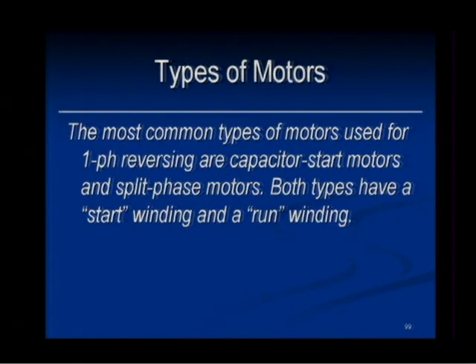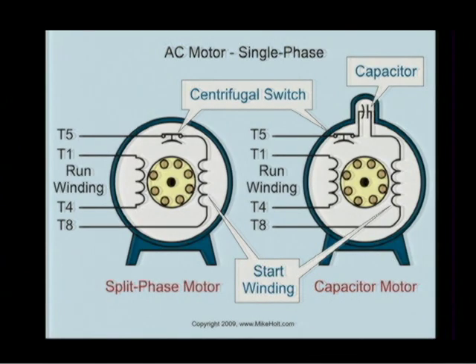The most common types of motors used for single-phase reversing are capacitor-start motors and split-phase motors. Both types have a start winding and a run winding. Are they actually numbered T1, T5, T4, and T8? Very commonly, there are some variations, but that's kind of a standard. But if they weren't this number, would it be marked somewhere? Is that on the nameplate? Nameplate, yes. It will tell you what the start winding is going to be and what the run winding is going to be.